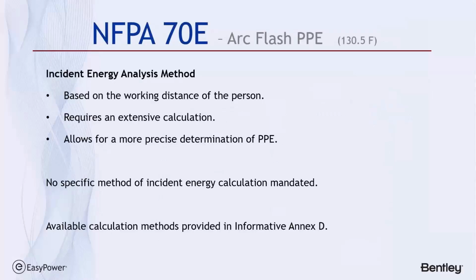Okay, which gets us to the incident energy analysis method. It's based on the working distance of the person. You're going to hear me refer to two different distances. One is the working distance that's listed on the label, and the other is the working distance that's needed or stipulated for hot work. They're seldom the same number, and it's important to understand what that means to somebody walking by the panel and looking at a label. The incident energy analysis method is fairly complex and requires extensive calculation.